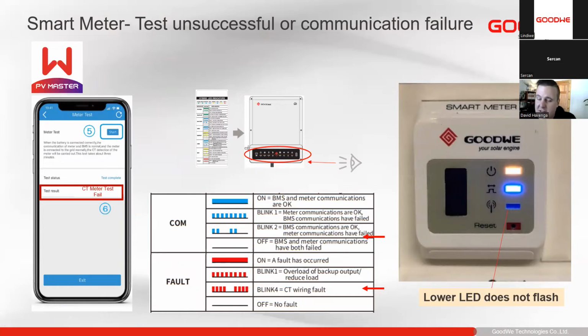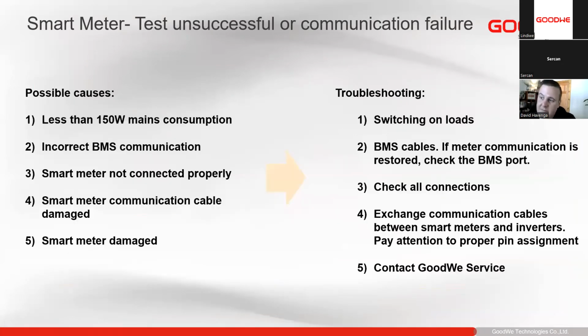So next we have the smart meter test, like I mentioned. Sometimes a smart meter test can fail for multiple different reasons. First of all, we need to make sure that our meter is communicating correctly with the inverter and that the BMS comms and everything is correct. The smart meter test does fail when we have less than 150 watts per phase consumption. So if our consumption from utility is too low, so if our PV is producing and we're zeroing the consumption from utility, and we run the meter test, it cannot accurately judge the direction of the CTs. We need to make sure we are consuming more than 150 watts per phase from the utility when we do the smart meter test. So very often we can put the solar off and then do the smart meter test.